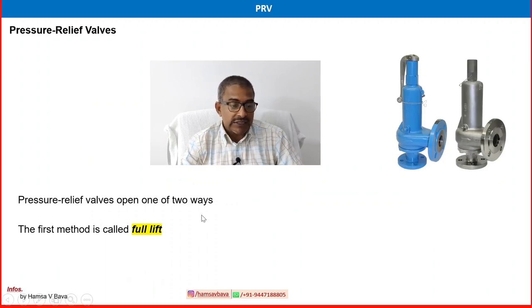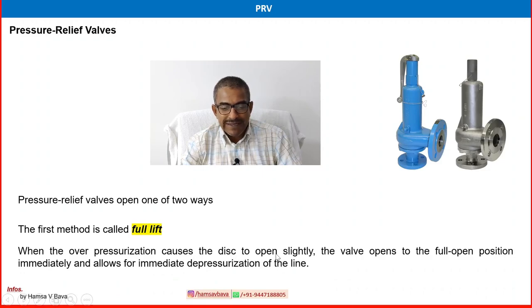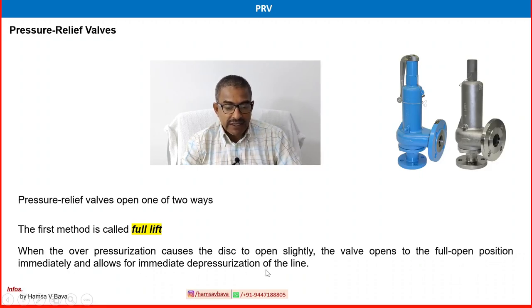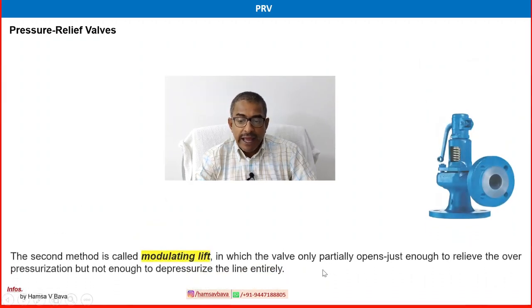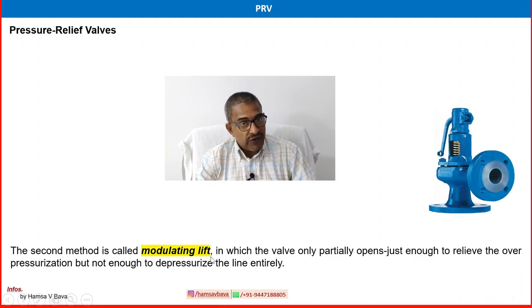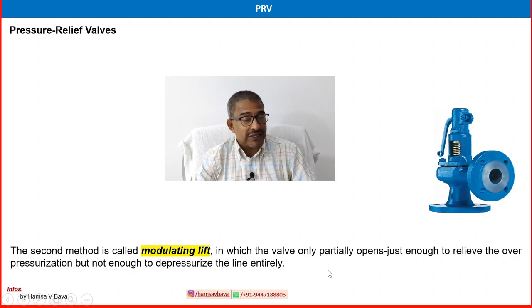Pressure relief valves open in two ways. The first method is called full lift — when overpressurization causes the disc to start opening slightly, the valve immediately moves to a fully open position allowing for immediate depressurization of the line. The second method is called modulating lift, in which the valve only partially opens — just enough to relieve the overpressurization but not enough to depressurize the line entirely.